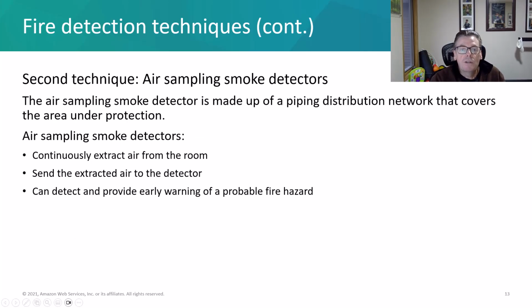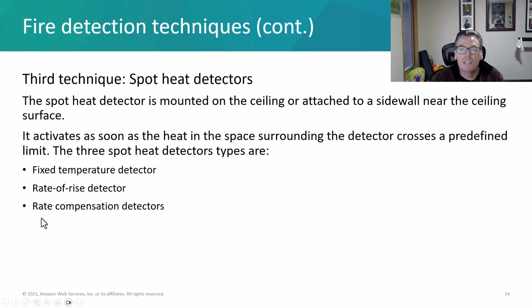All right, the second thing we can use is an air sampling smoke detector. The air sampling smoke detector is made up of a distribution network that covers the areas it is protecting. They continuously extract air from the room and send that extracted air to the smoke detector, which can detect and give you an early warning of a probable fire hazard. So if it's detecting smoke, it can raise the alarm.